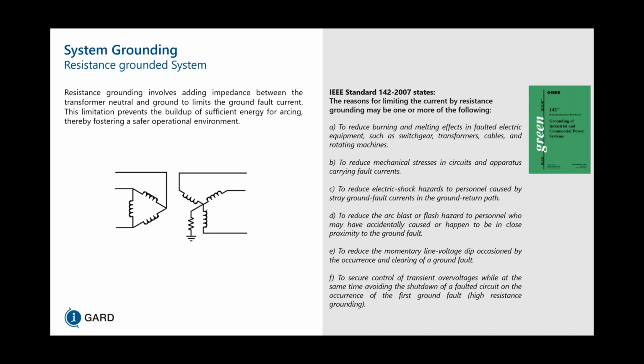Now, in the Green Book by IEEE, the reasons for limiting the current by resistance include the following: to reduce burning and melting effects in faulted electrical equipment, such as switchgear, transformers, cables, and rotating machines; to reduce mechanical stresses in circuits and apparatus carrying fault currents; to reduce electrical shock hazards to personnel caused by stray ground fault currents in the ground return path; and most importantly, to reduce the arc blast or flash hazard to personnel who may have accidentally caused or happen to be in close proximity to the ground fault.